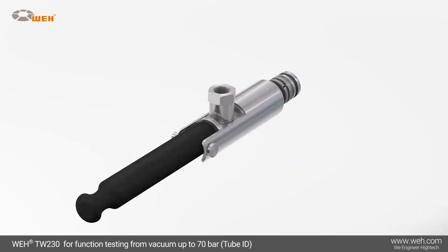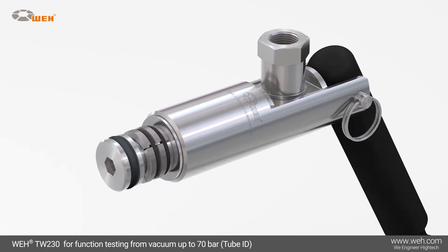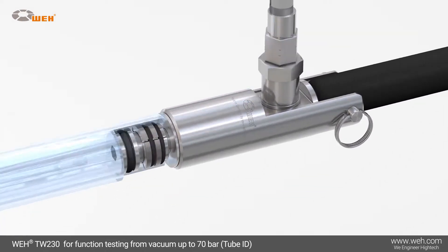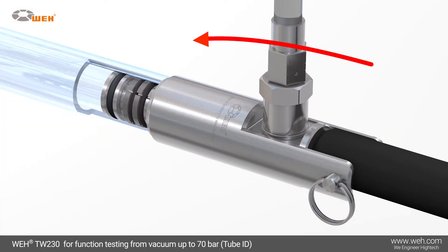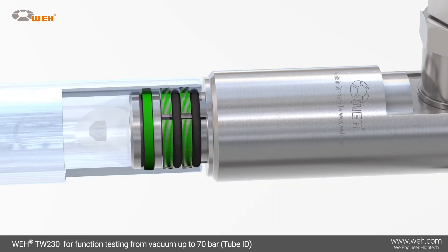The WEH TW230 quick connector is suitable for underwater, pressure decay, and helium testing at high-pressure ranges up to 70 bar. By sealing the inner tube diameter and bores, the radial sealing system works reliably and effectively.